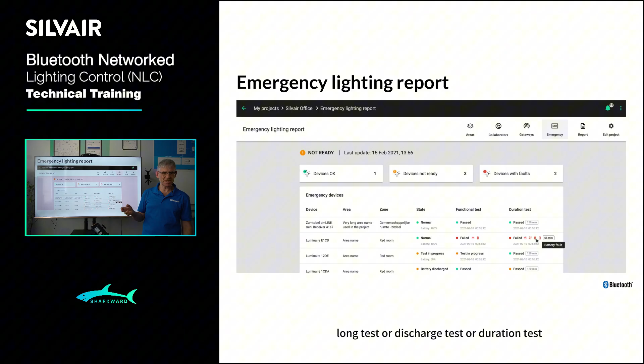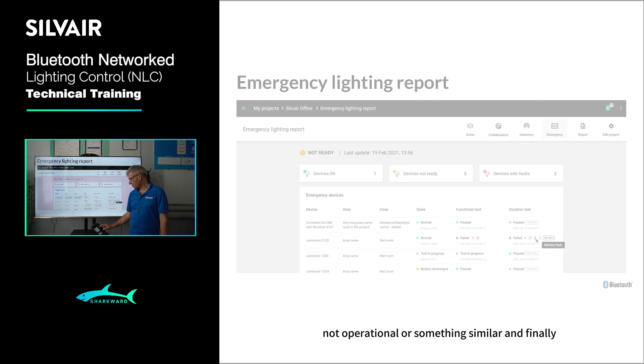In different legislations, the time requirements are different. Most typical are 90-minute or 2-hour duration tests. We support all that. And then the report is produced, and we can see here all statuses from all devices, including if there are some faults. We can see the fault reason, for example, battery fault or some other issues like the light source not operative or something similar.